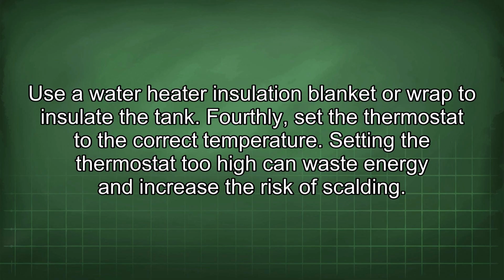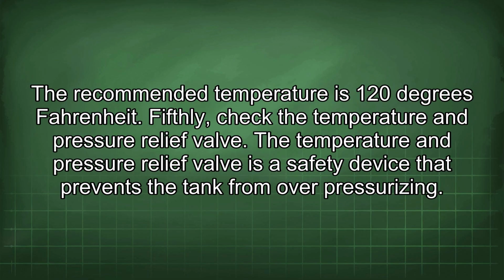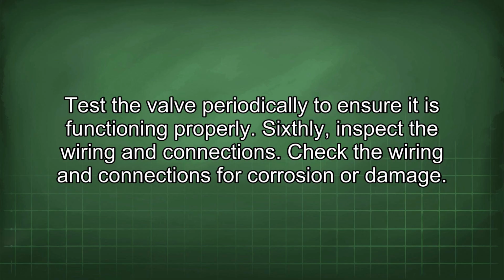Fourthly, set the thermostat to the correct temperature. Setting the thermostat too high can waste energy and increase the risk of scalding. The recommended temperature is 120 degrees Fahrenheit. Fifthly, check the temperature and pressure relief valve. The temperature and pressure relief valve is a safety device that prevents the tank from overpressurizing. Test the valve periodically to ensure it is functioning properly.